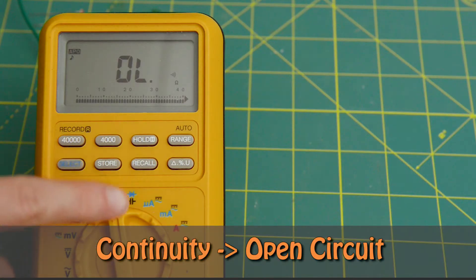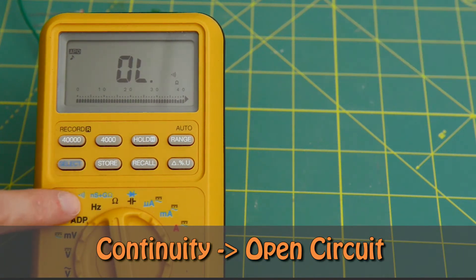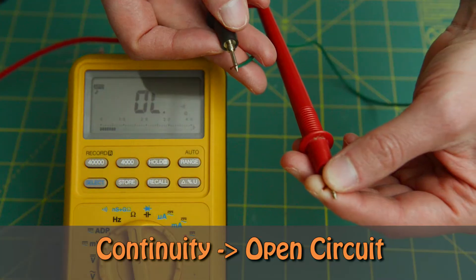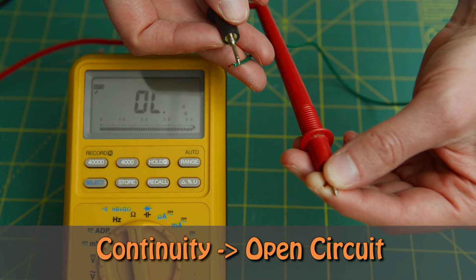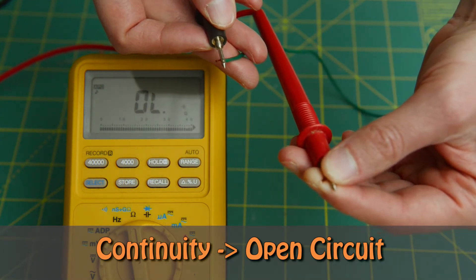To do our testing, we're going to use a digital multimeter. You change your setting to the resistance setting, and then you hit select twice to go to the audible tone, and that will tell you that your circuit is completed. So that sound tells us that we don't have any opens in that segment of our circuit, and the electricity is going from one end of the wire to the other.